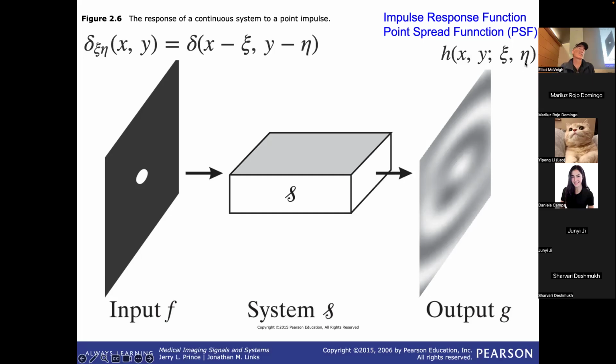And in optics, if you've had a set of cheap binoculars, or when you were a kid, you had a really cheap microscope, you know that those systems are not shift invariant, right? You need to put the lens right on your target, because if you go off to the edge a bit, it starts to blur, right? And so you have a different point spread function depending on where the object is in the field of view, right? And if that occurs in our CT scanner, such that my little ballpoint pen right in the middle of the scanner versus way off at the edge of the scanner produces a different point spread function, impulse response function, then that is not shift invariant.